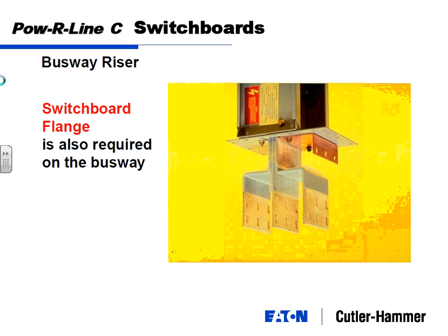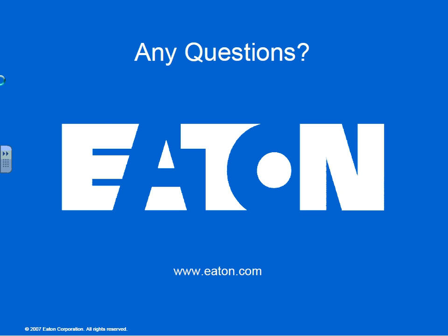And here's kind of what it looks like. Panel boards have to be cables, but switchboards have the ability for a busway connection, and that's really just the takeaway on this. Here's kind of visually what we're looking at. This is a busway up top, and you can see the copper bars coming out. When the busway is running across the ceiling, they're all sandwiched together. When you come down into the switchboard, they spread out to follow the air clearances that are required inside the switchboard. So it's a bolted connection. That's it for that.